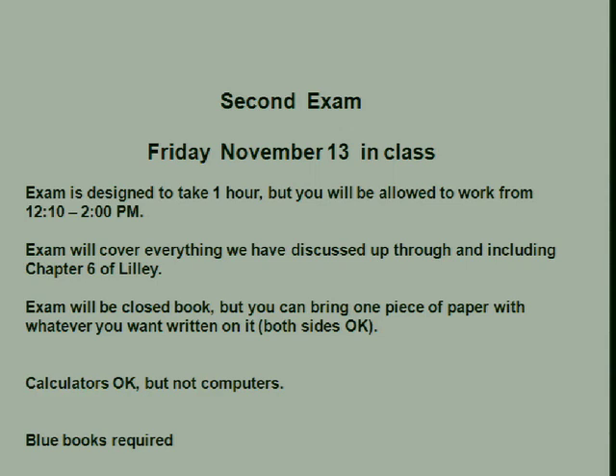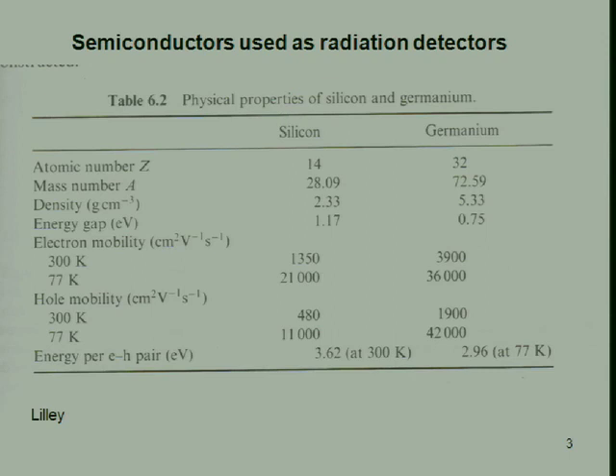Okay, so on Friday we talked about two classes of detectors: ionization counters, and then scintillation type detectors. I showed you sodium iodide and plastic scintillation detectors, and we talked about the relative merits of each. The plastic scintillators are cheap, rugged. Sodium iodide detectors are more sensitive to environmental issues. They don't like humidity, they don't like water, they don't like being banged around, but they offer much better energy resolution than the plastic.